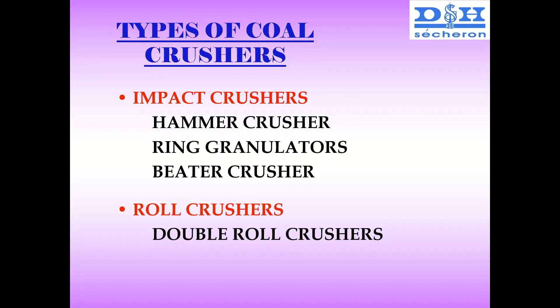Another type found in many power plants is the roll crusher. There are two strong rolls through which the material is passed and asked to crush. It is very similar to sugar cane crushing. The crusher rolls are made of manganese steel — heavy-duty rolls. When coal passes inside, due to the pressure applied, coal gets broken and reduced to a smaller size as per the requirement for the coal mill.